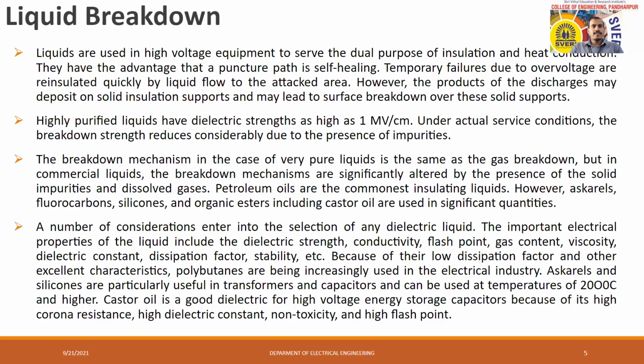Then, as we know about gas and vacuum breakdown, there is also liquid breakdown. By using liquid as an insulating medium, the major purposes behind that are insulation and heat conduction. Liquid has very good merits in that its puncturing path is self-healing. So whatever temporary failure occurs, if there's overvoltage, overcurrent, or overload, the liquid will flow to the affected area and transmit its heat. With that, whatever discharging occurs will be surface discharging, or surface breakdown, on the solid supports or surface of the solid material.